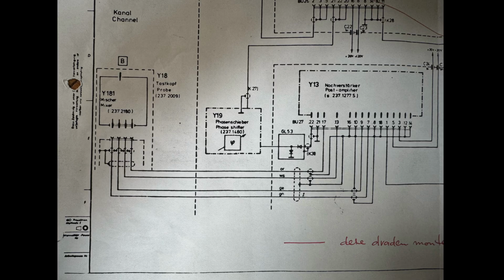And if I look at some more of the schematics of the device on the right hand of your screen, you also see again the same post amplifier that I was just looking at. But then you see four, they are small, four isolated wires going into the measurement probe. And that is apparently the signal coming from the probe and the signals going back, like bias and impulse type of signals. But the real magic seems to be happening within the probes themselves, in the testkopf probe. And that is the only part of the schematics basically that we don't find in the manual of the device. We don't see the precise way these things work here. But later I'll dissect the device a little bit more and we get to learn a little bit more about the actual way that the sampling head is working.